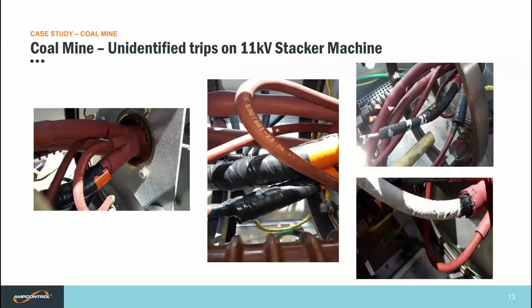The next slide, we have some of the photos from that site. What you can see here is that the site thought there may be an issue with the high voltage causing some sort of spike through the control cable. So they've applied a piece of PVC insulation and then wrapped it in 23 tape. What that has done has decreased the air clearance between your phases and actually to the control cores.